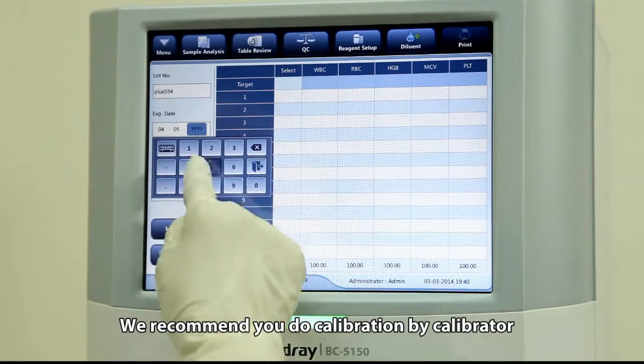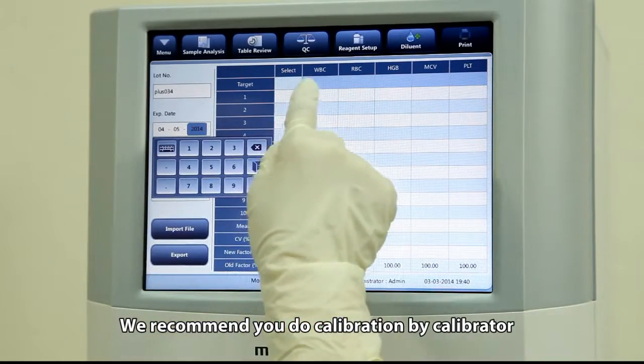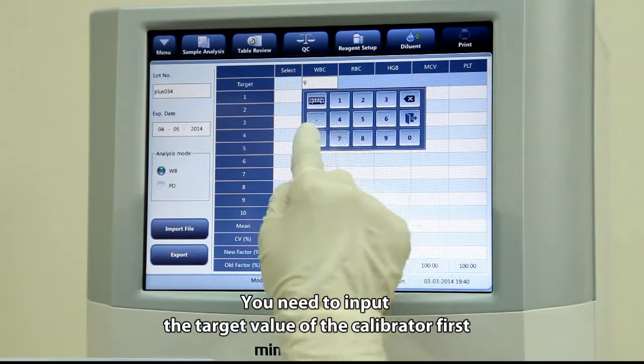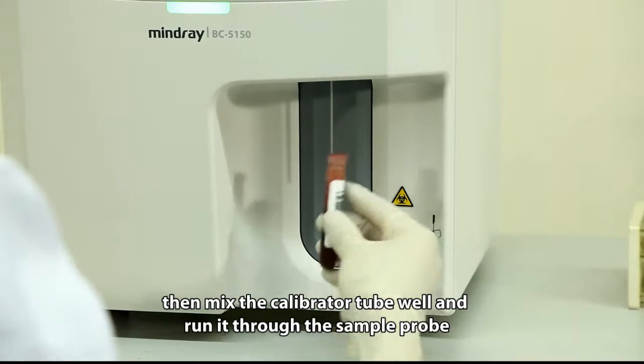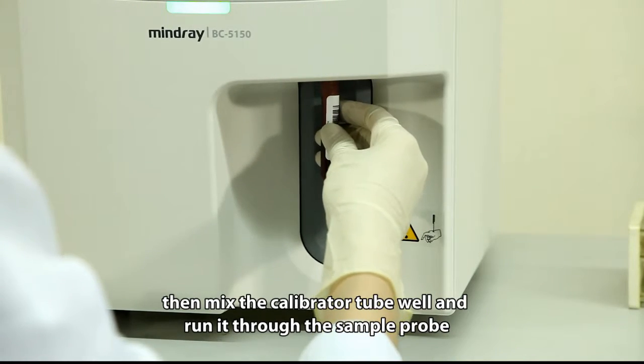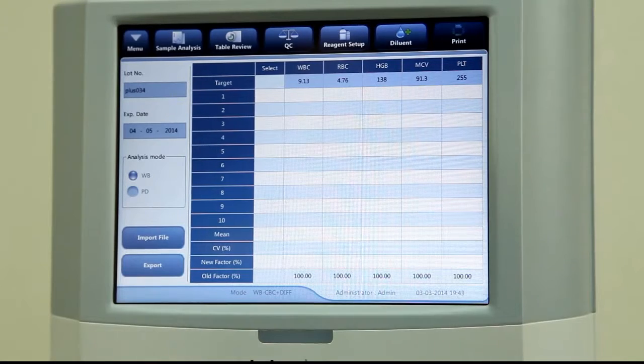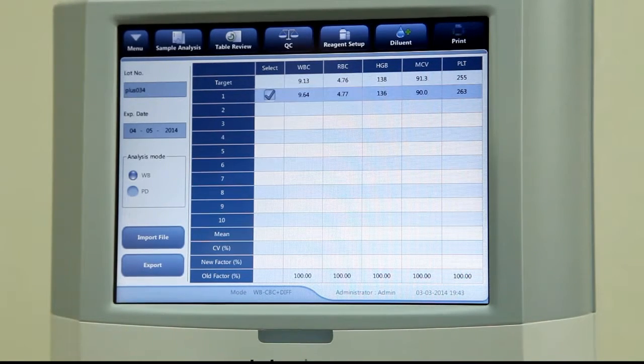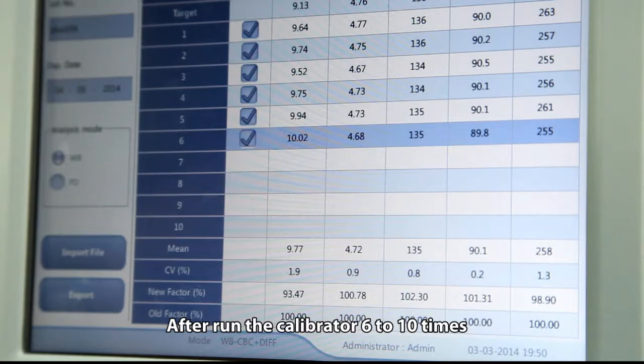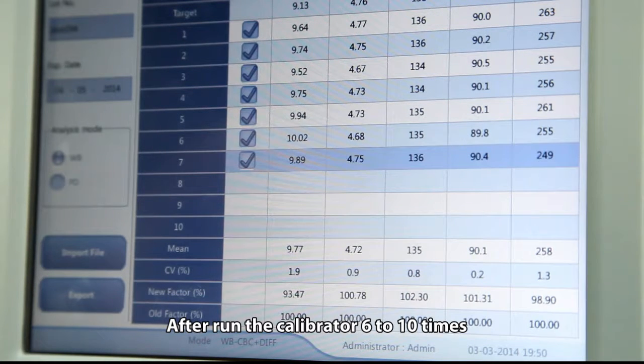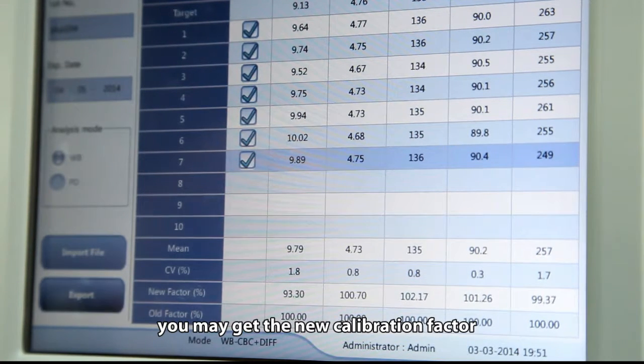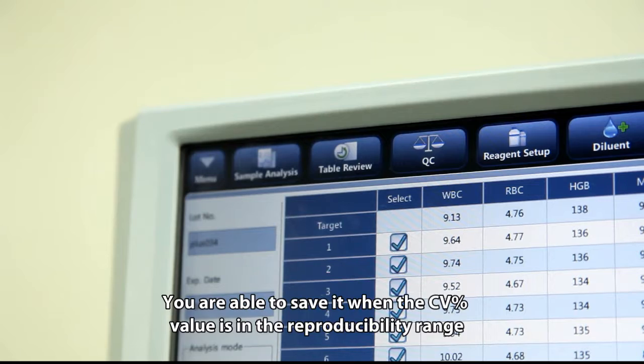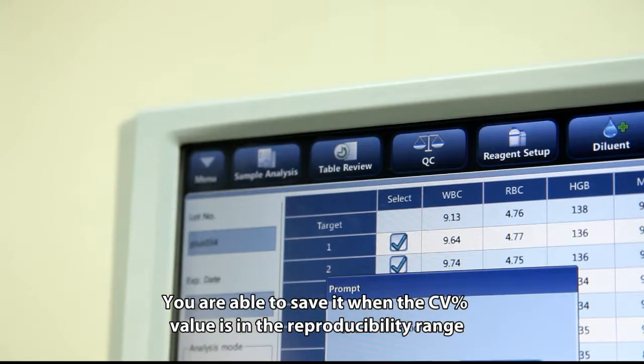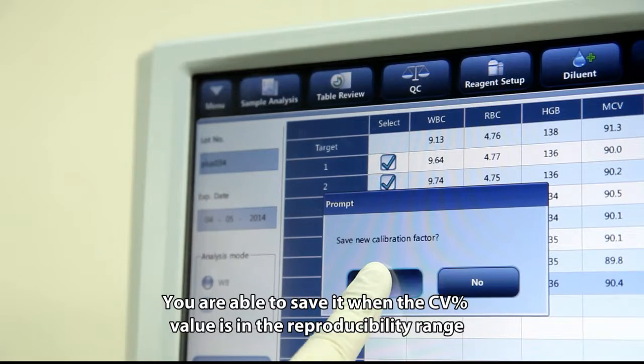We recommend you do calibration by calibrator. You need to input the target value of the calibrator first, then mix the calibrator tube well and run it through the sample probe. After running the calibrator 6 to 10 times, you may get the new calibration factor. You are able to save it when the CV% value is in the reproducibility range.